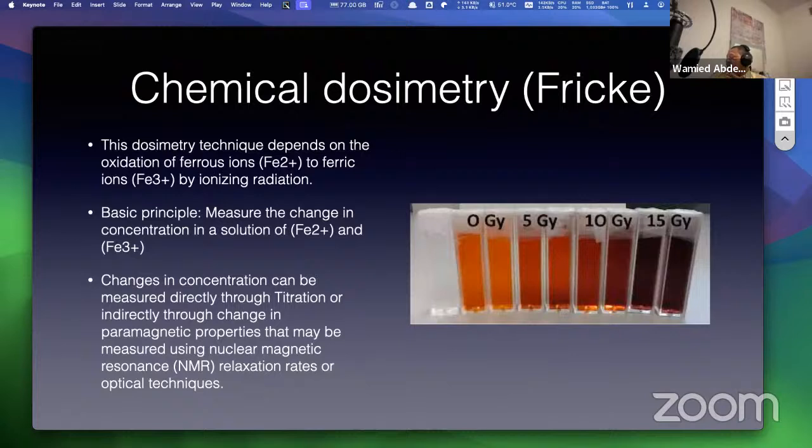I think today we have these optical CTs as 3D dosimeters. So what we can do is take, for example, a light beam or a laser, and let it go through the solution when there is no dose. Once this dosimeter is irradiated, its opacity will change, it becomes darker. So the transmission of the same light intensity is going to change.